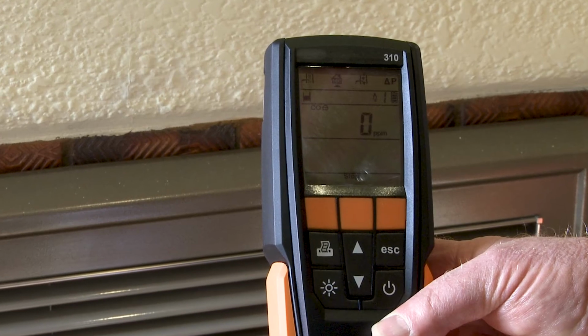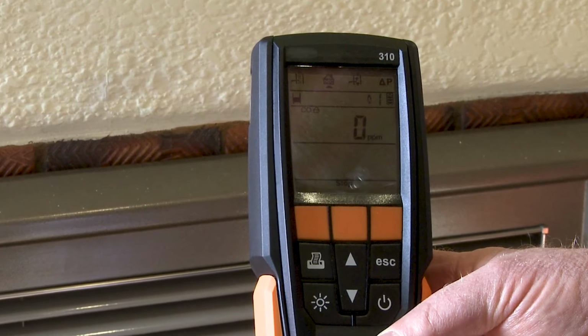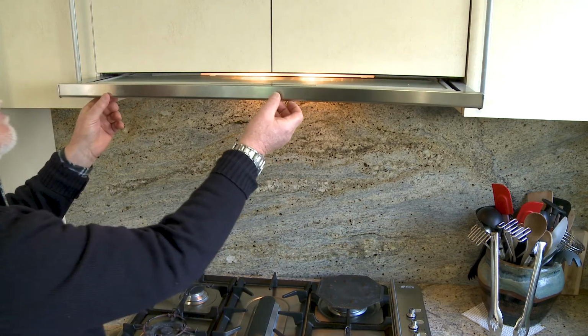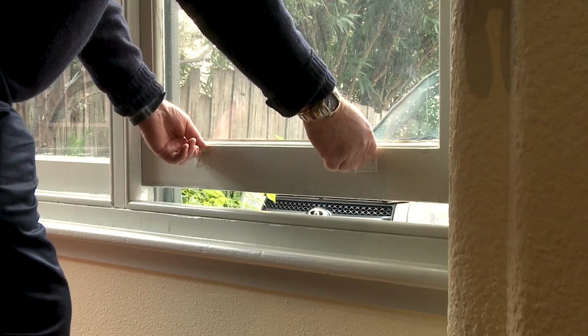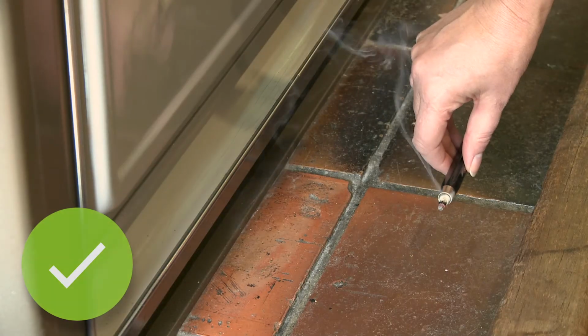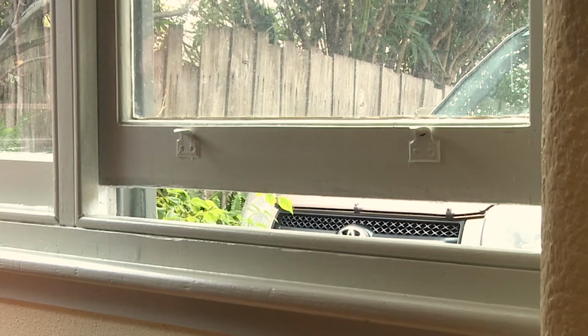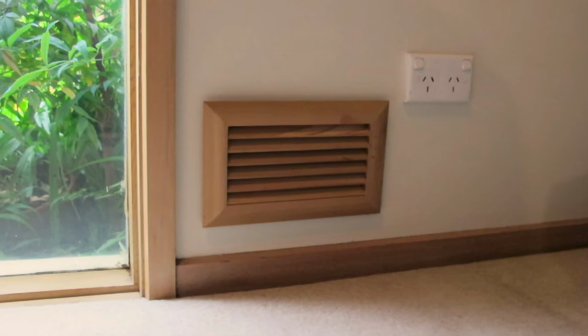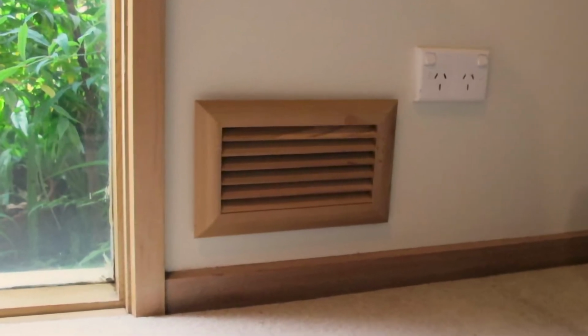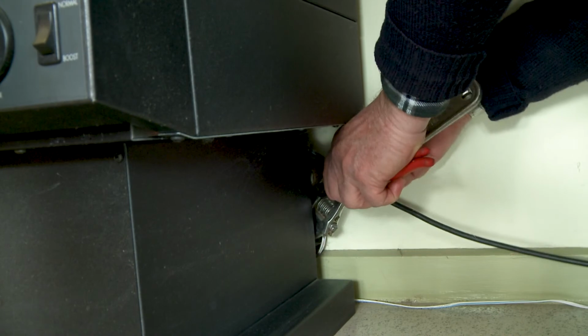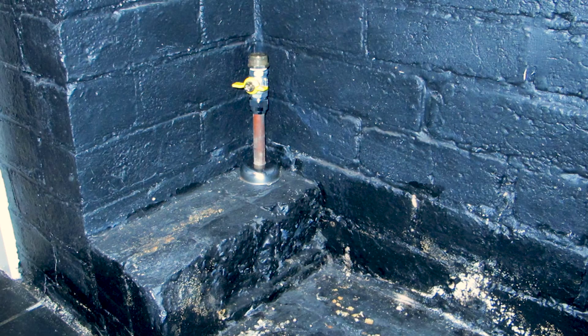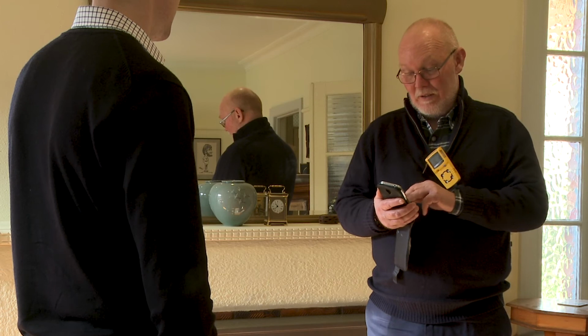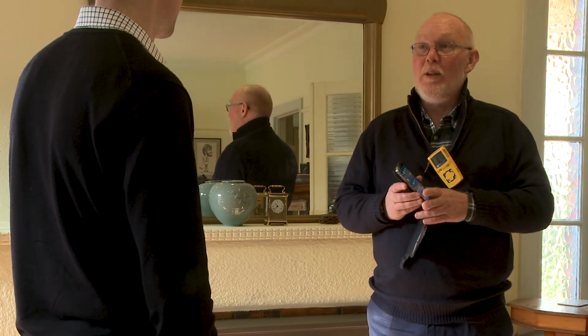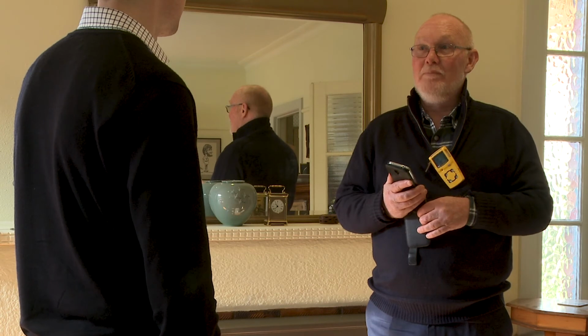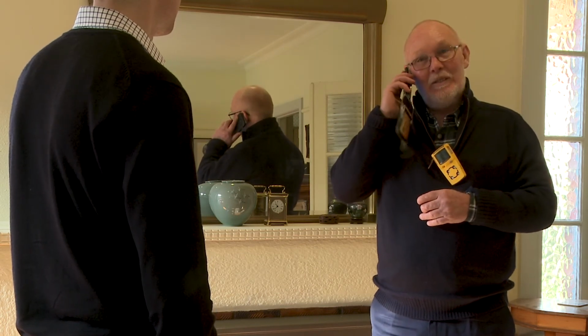If there is no spillage, this means there is still a negative pressure environment. Switch on all exhaust fans to their highest settings and progressively open the window until you've cancelled the negative pressure situation. Additional permanent ventilation equal to the area of the window opening must then be installed. If you can't install the required ventilation on the spot, then you must make the appliance safe. You'll need to do this by isolating it. Where an owner refuses to allow you to isolate the appliance, you must notify the relevant authority, as explained in the Combustion Testing Learning module.